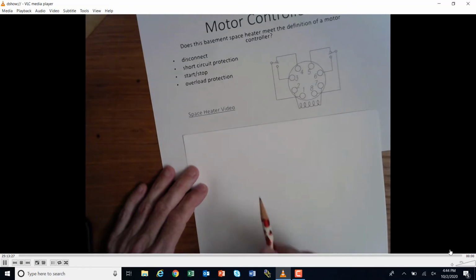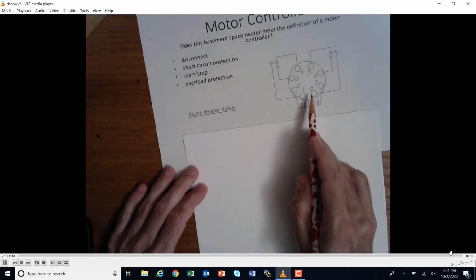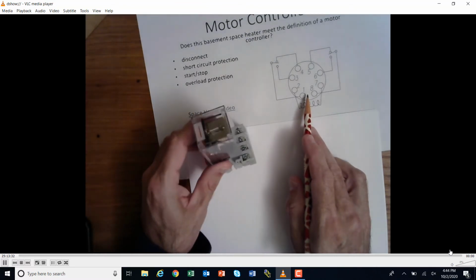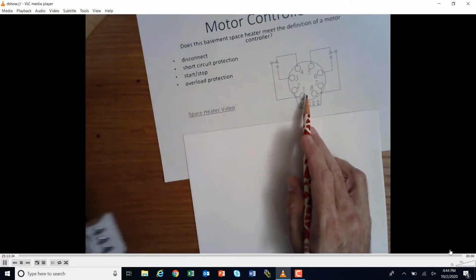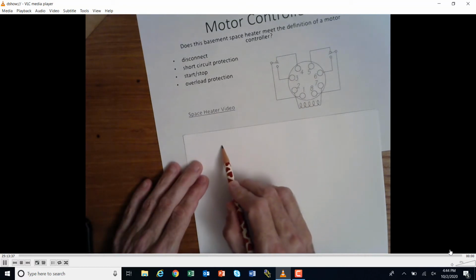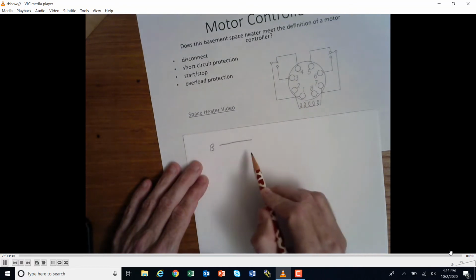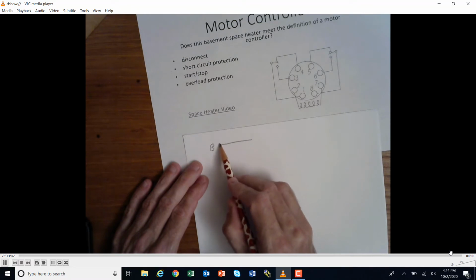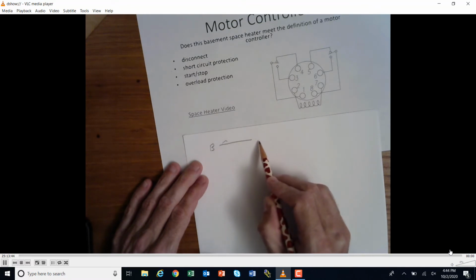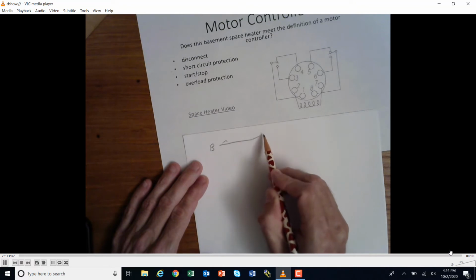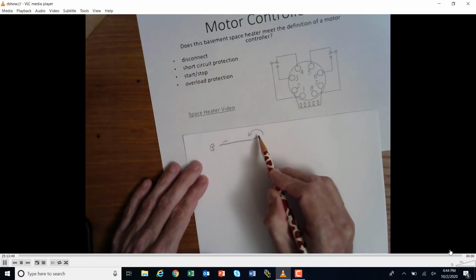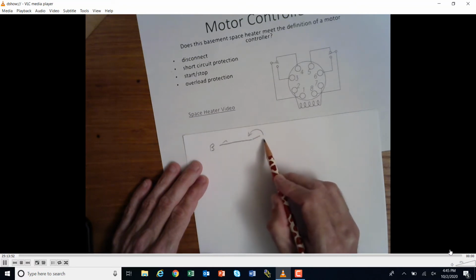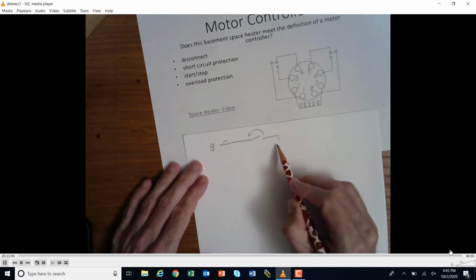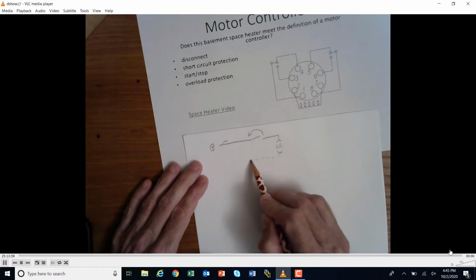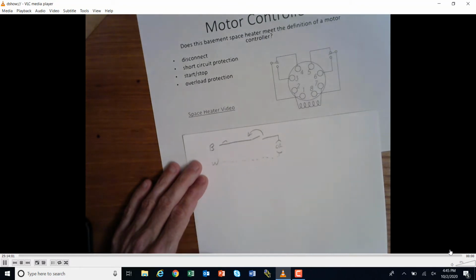When I went to my breaker box, the control relay I used was a 120 volt relay. So what I did was run the black wire from the circuit box, which is on a circuit breaker, through my switch, and I put a little dial there so that switch closes for 5 minutes, 10 minutes, or whatever. Then I ran that to the control relay, and it comes back to the box as white because that was my neutral.